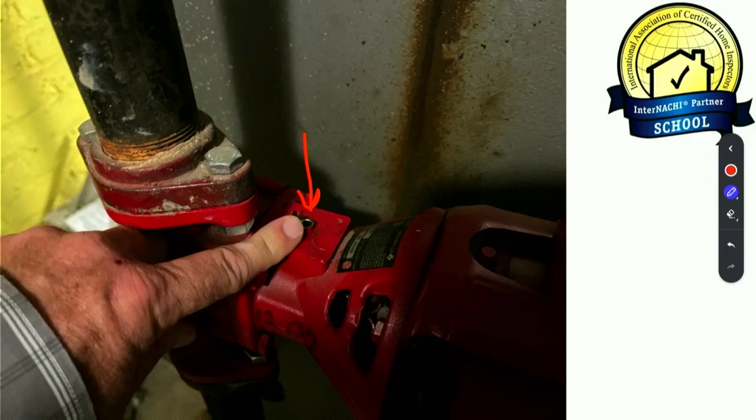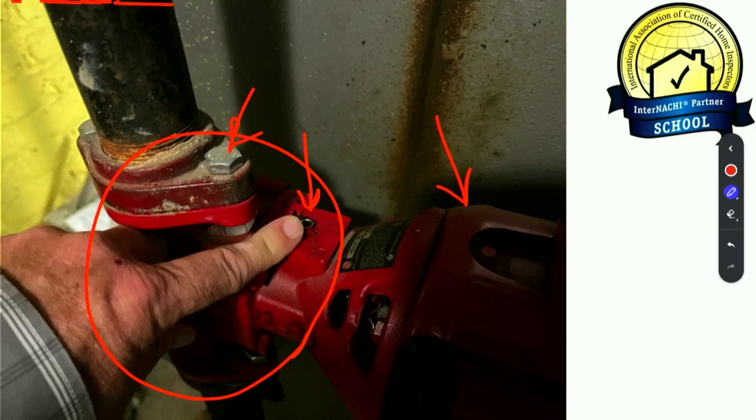And then once you let it go at that for a little bit, then we're going to start seizing our pump. And once we're doing that, now we're going to have to be undoing some bolts and replacing the whole pump once that thing's seized. Most of the problems we're going to get are going to be with the motors themselves. And if somebody's confident enough to switch out a light switch or an outlet, replacing these motors is really not all that difficult. So I do what I can to talk them into having a spare motor sitting there ready to go. Because when they fail, it's always going to be at 2 o'clock on Christmas morning, when you don't have a service guy available and now you're without heat.